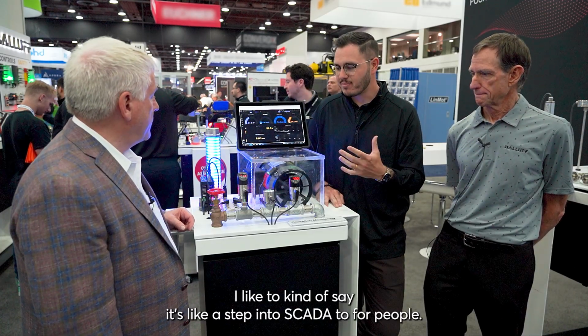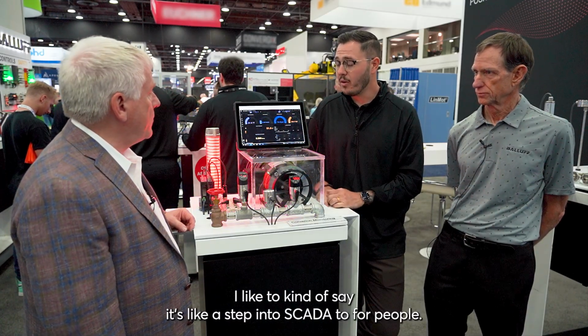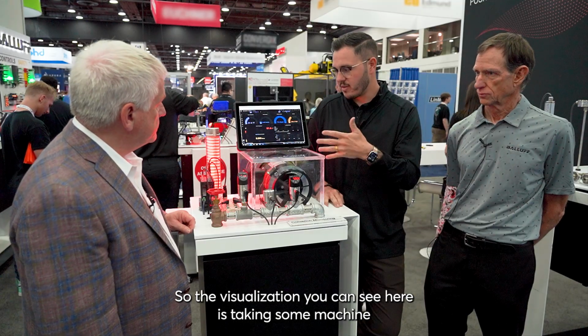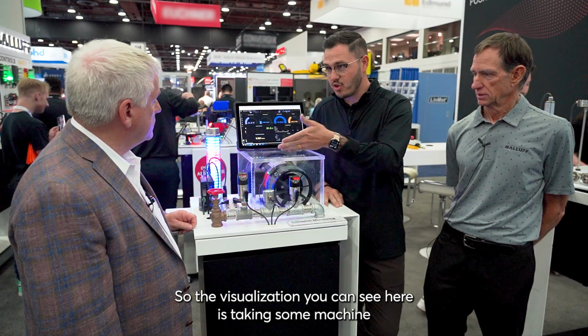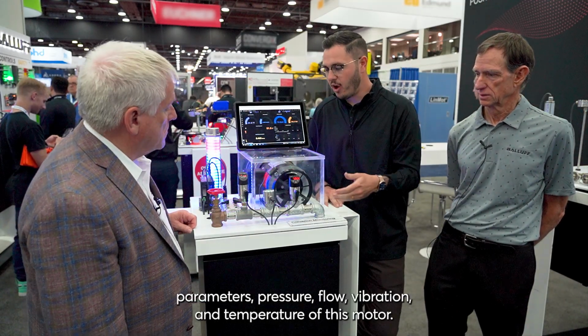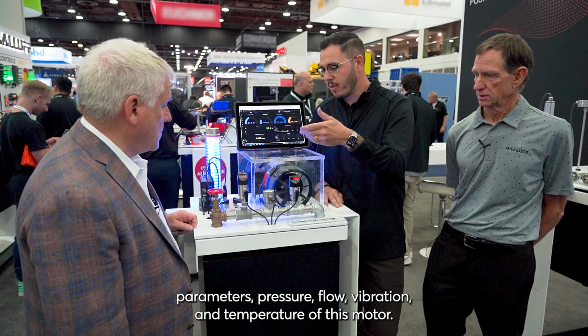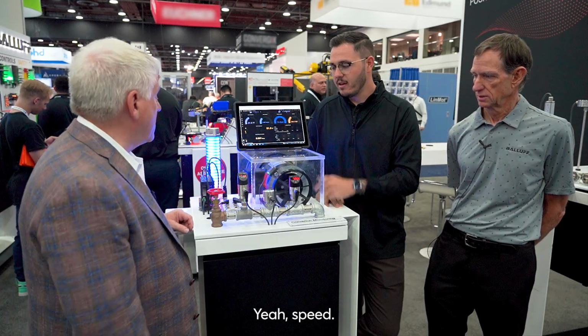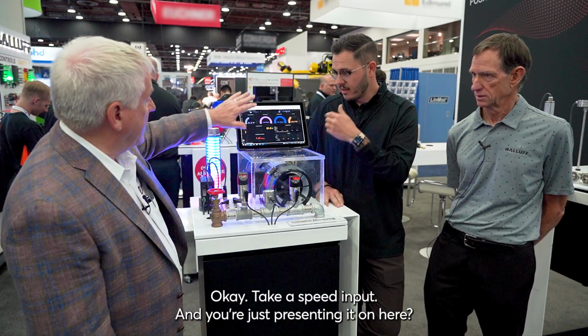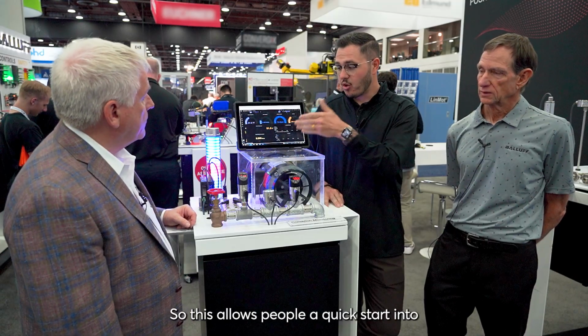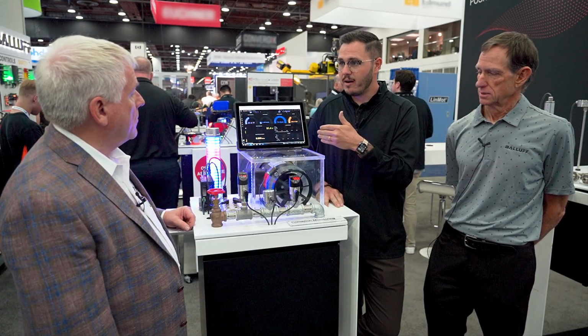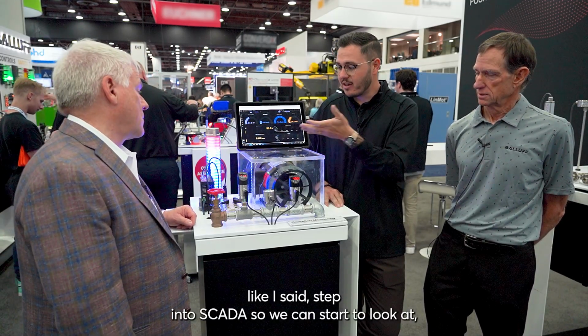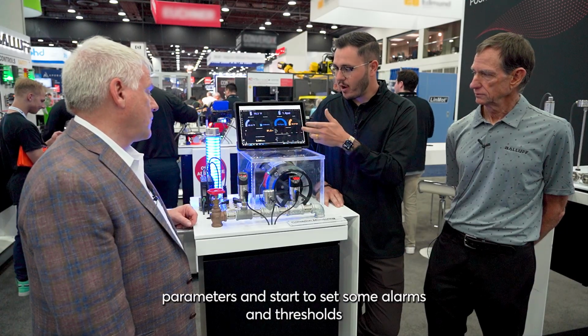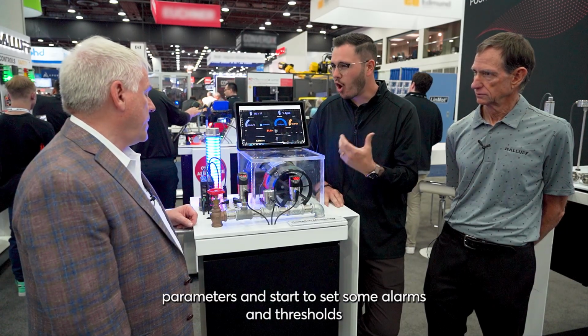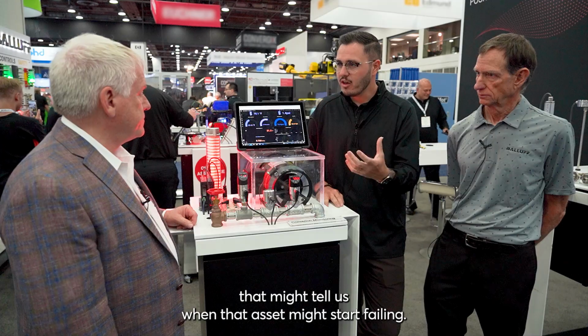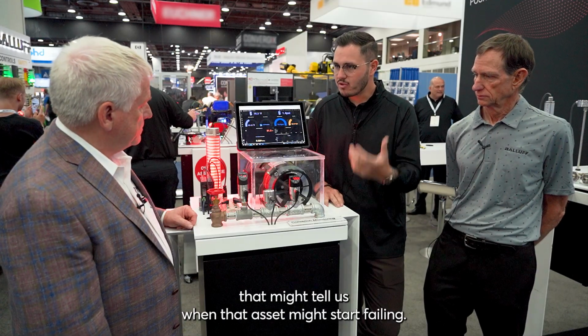It's essentially an edge gateway with a free visualization software on it. I like to say it's a step into SCADA for people. The visualization you can see here is taking some machine parameters, pressure, flow, vibration, and temperature of this motor. Or speed. Yeah, we take a speed input. And you're just presenting it on here. Yeah, so this allows people a quick start into that step into SCADA. We can start to look at parameters and set some alarms and thresholds that might tell us when that asset might start failing.